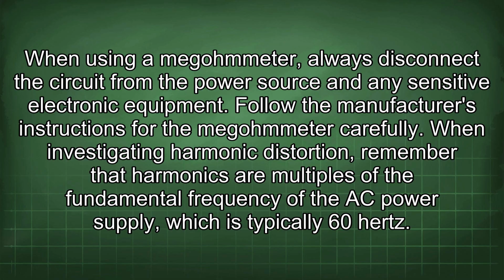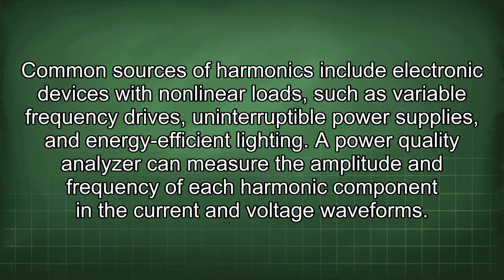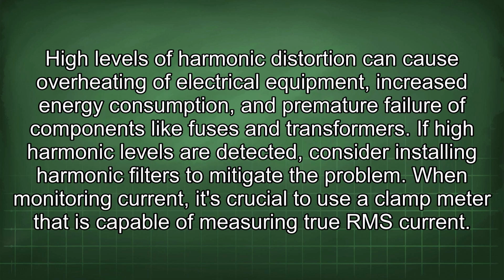When investigating harmonic distortion, remember that harmonics are multiples of the fundamental frequency of the AC power supply, which is typically 60 Hz. Common sources of harmonics include electronic devices with nonlinear loads such as variable frequency drives, uninterruptible power supplies, and energy-efficient lighting. A power quality analyzer can measure the amplitude and frequency of each harmonic component in the current and voltage waveforms. High levels of harmonic distortion can cause overheating of electrical equipment, increased energy consumption, and premature failure of components like fuses and transformers. If high harmonic levels are detected, consider installing harmonic filters to mitigate the problem.